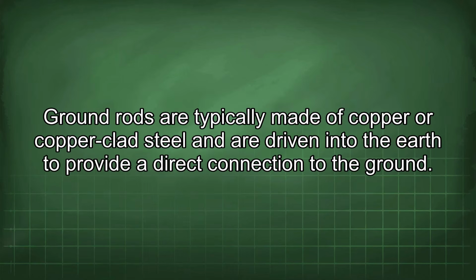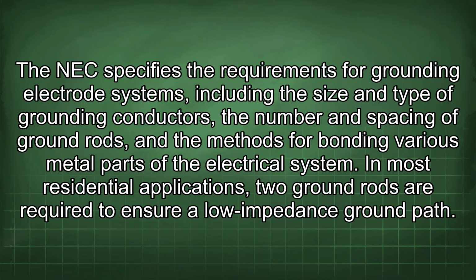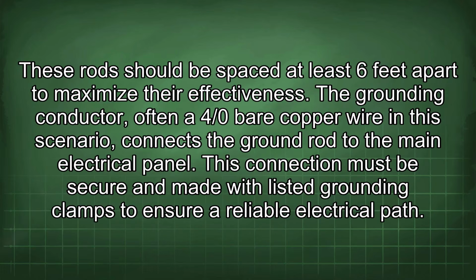Ground rods are typically made of copper or copper-clad steel and are driven into the earth to provide a direct connection to the ground. The NEC specifies the requirements for grounding electrode systems, including the size and type of grounding conductors, the number and spacing of ground rods, and the methods for bonding various metal parts of the electrical system. In most residential applications, 2 ground rods are required to ensure a low-impedance ground path. These rods should be spaced at least 6 feet apart to maximize their effectiveness.